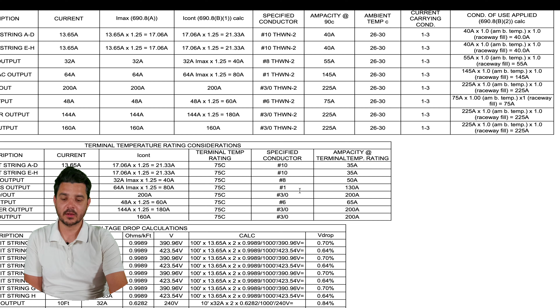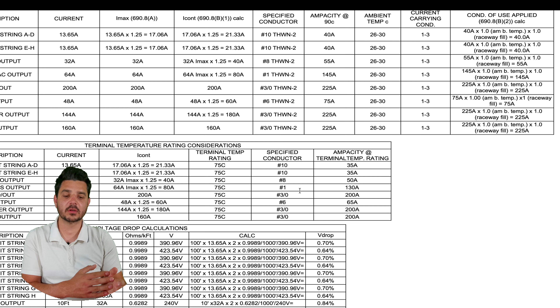Franklin's, we're using number 6s. You got 3-aught. We kept a lot of the batteries near the equipment. The only thing that's a little far away are those Tesla Solar Inverters, and number 8 should be fine with little to no voltage drop.